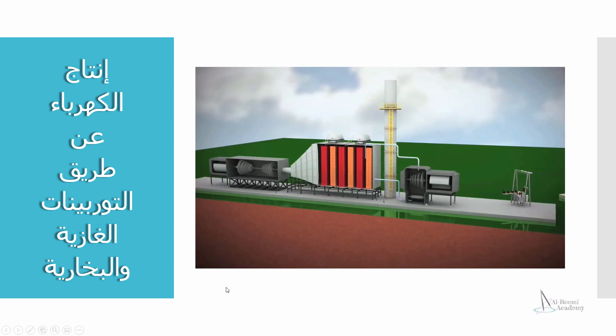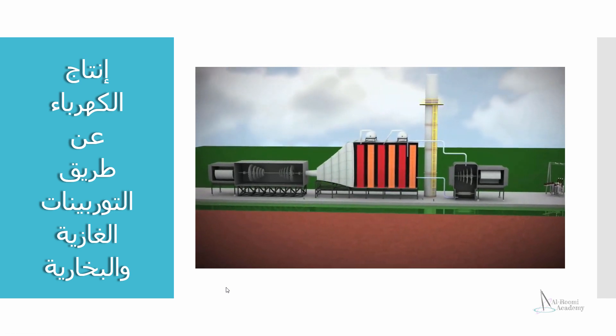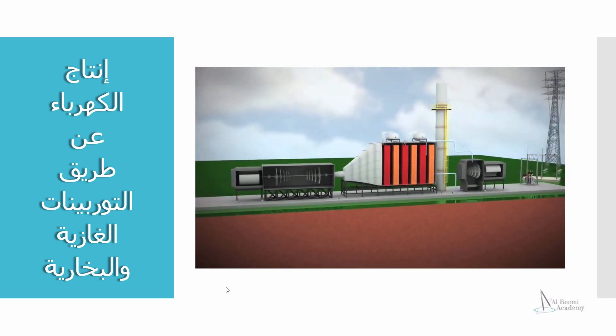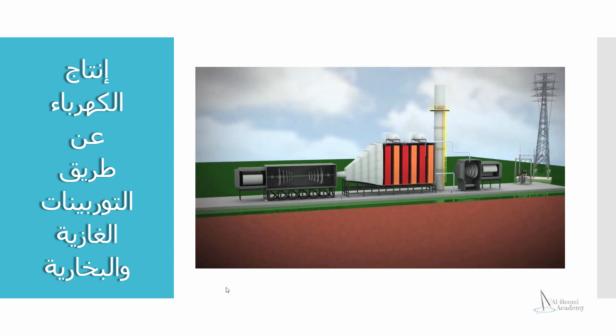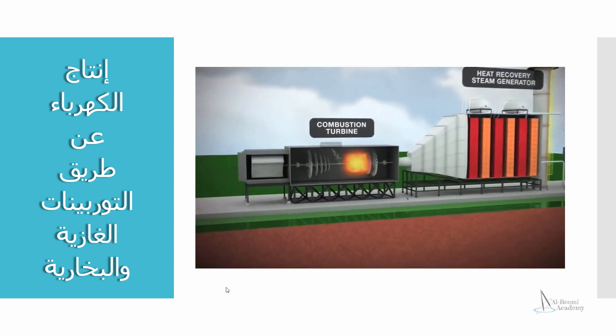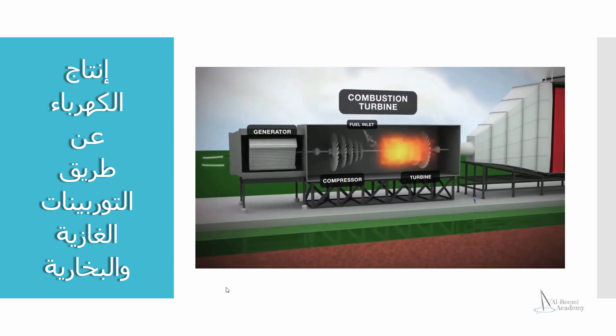The combined cycle turbine technology enables power plants to generate 50% more electricity from its fuel than it would with a conventional single-cycle power system. Under this dual-phase system, two combustion turbine generators operate in conjunction with two heat recovery steam generators and a steam turbine generator. In the first cycle, fuel is burned, and the resulting combustion gases power two turbine generators to produce electricity.